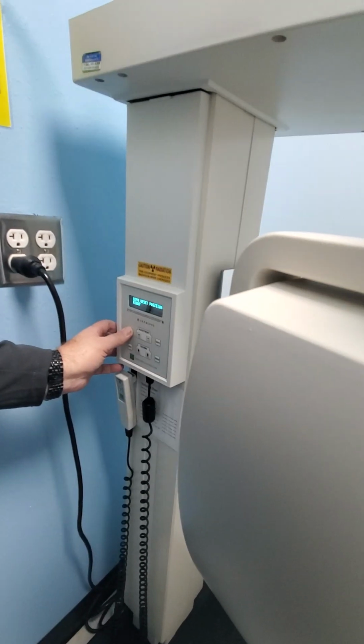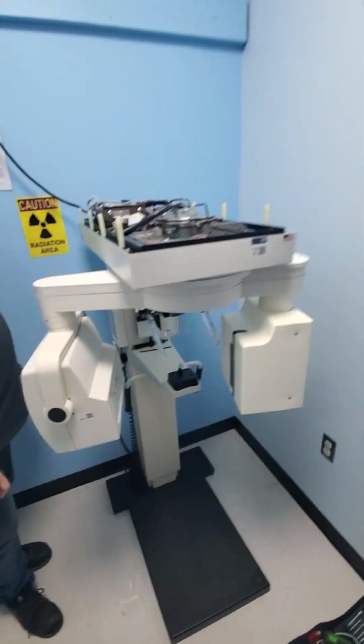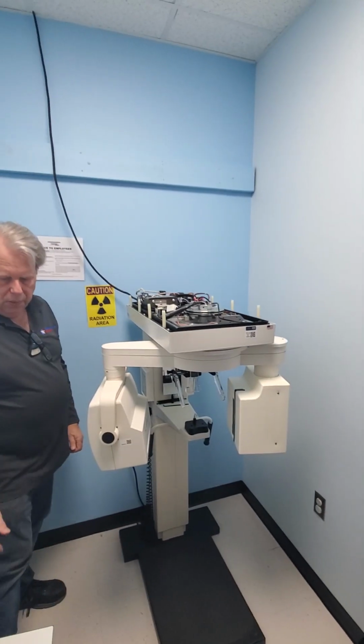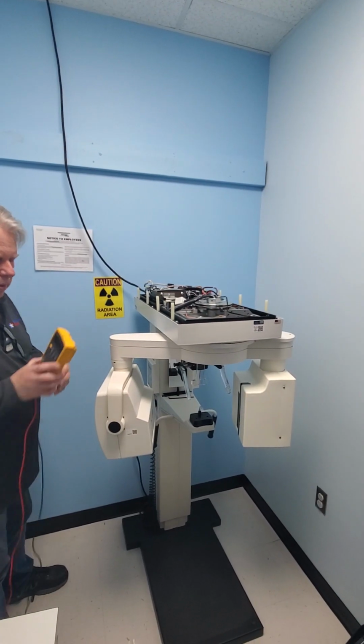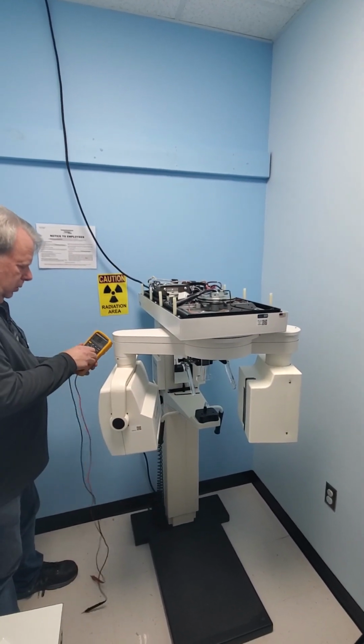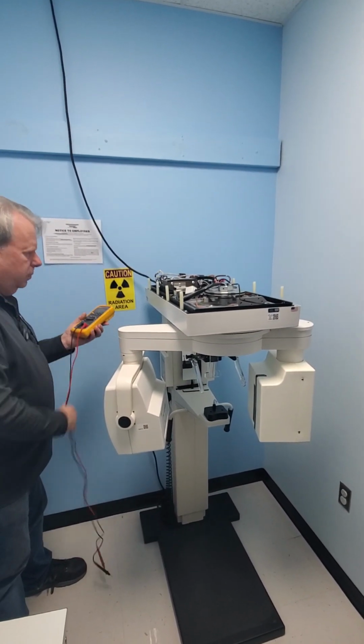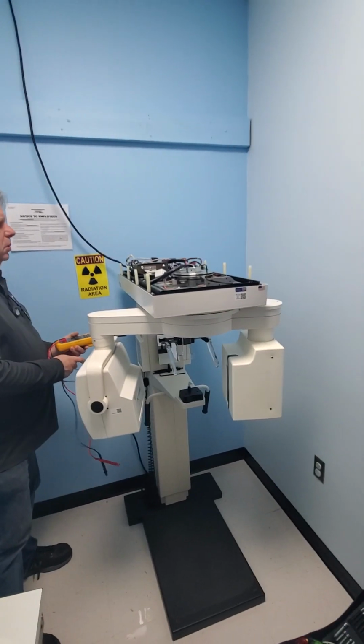Let's look at the KVP again and see. So to recap, what we've actually done, number one, the KV adjustment to get it accurate was way off. Yeah, and there's two adjustments for that, the 89 and the 104, correct? Right. And then the next step is to check the MA.